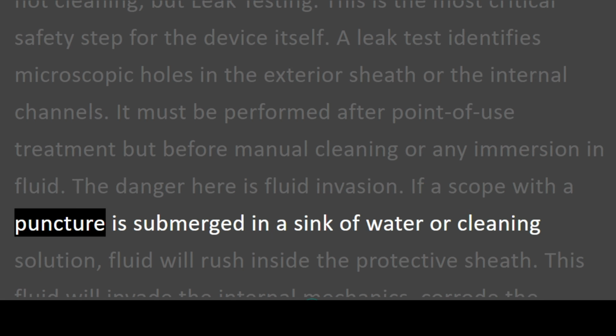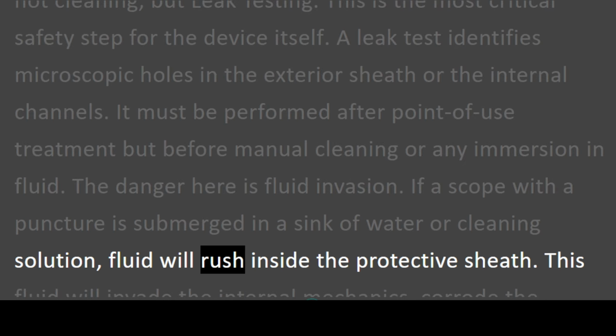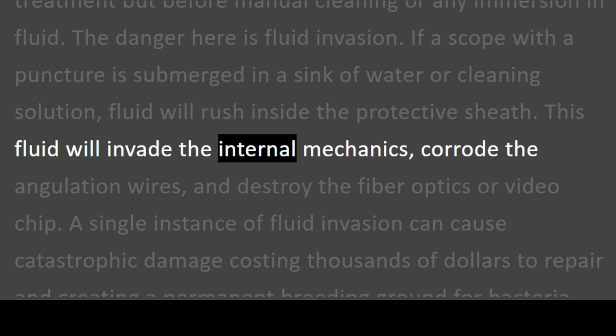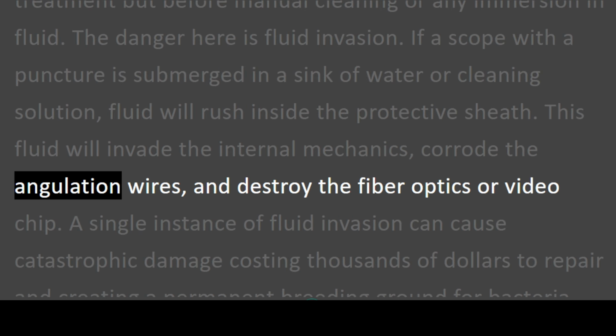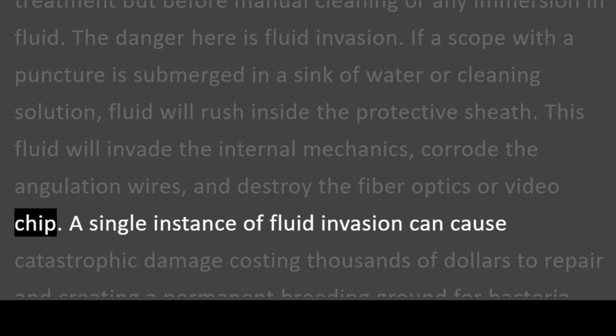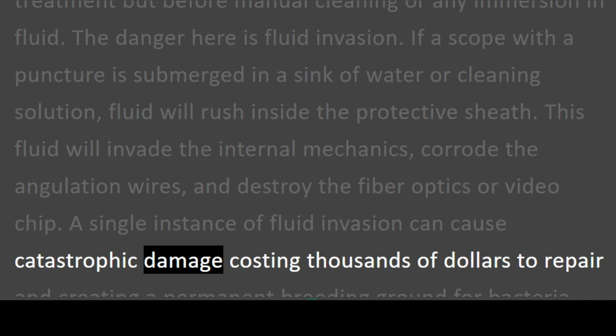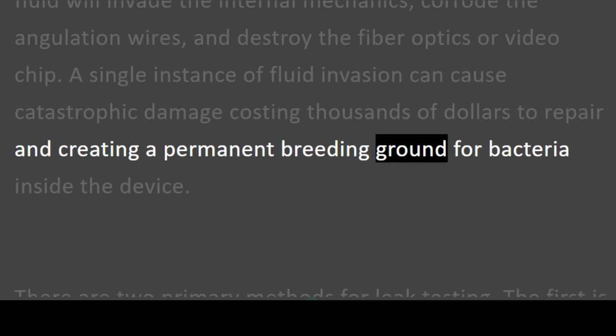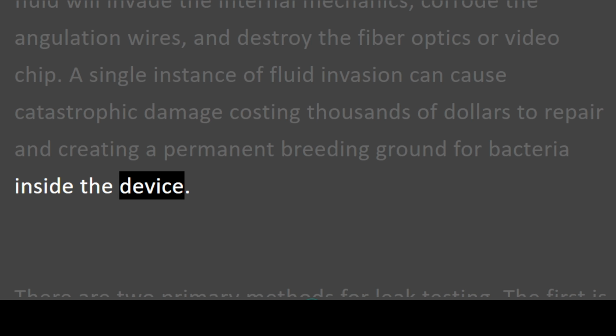If a scope with a puncture is submerged in a sink of water or cleaning solution, fluid will rush inside the protective sheath. This fluid will invade the internal mechanics, corrode the angulation wires, and destroy the fiber optics or video chip. A single instance of fluid invasion can cause catastrophic damage, costing thousands of dollars to repair and creating a permanent breeding ground for bacteria inside the device.